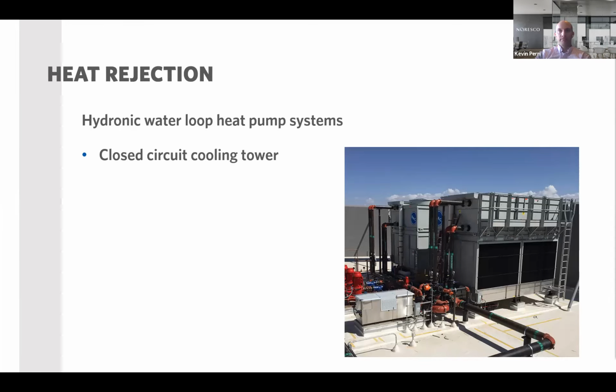Okay, heat rejection. So hydronic water loop heat pump systems, they've added a section to this. They added a closed circuit cooling tower to the requirements for this section. Before it was just an open circuit cooling tower. Now closed circuit cooling towers have to follow this heat rejection system, when they're used in conjunction with a separate heat exchanger to isolate the open circuit cooling tower from the heat pump loop. Again, just a slight addition that you're probably already familiar with.